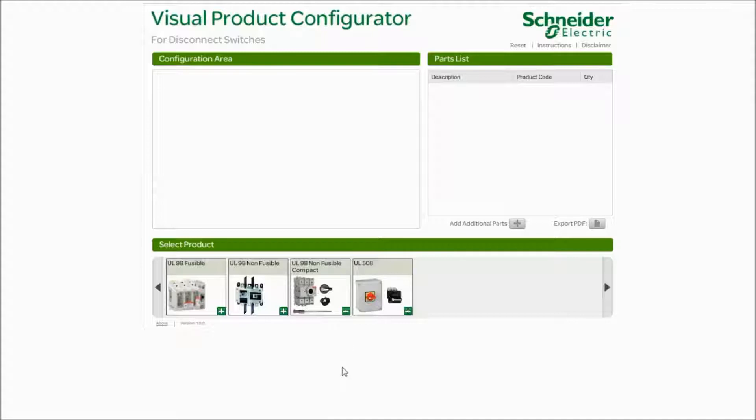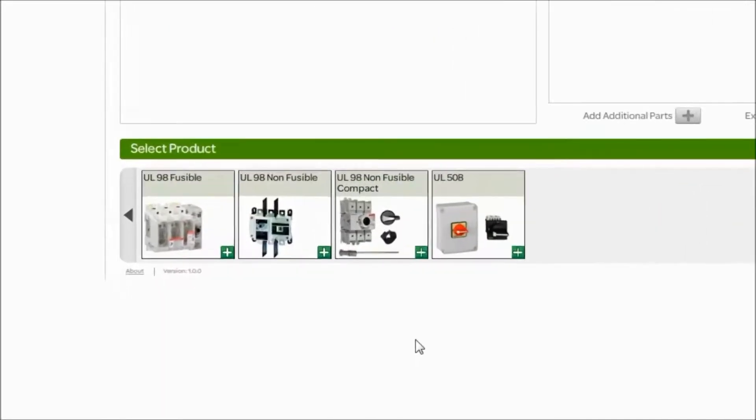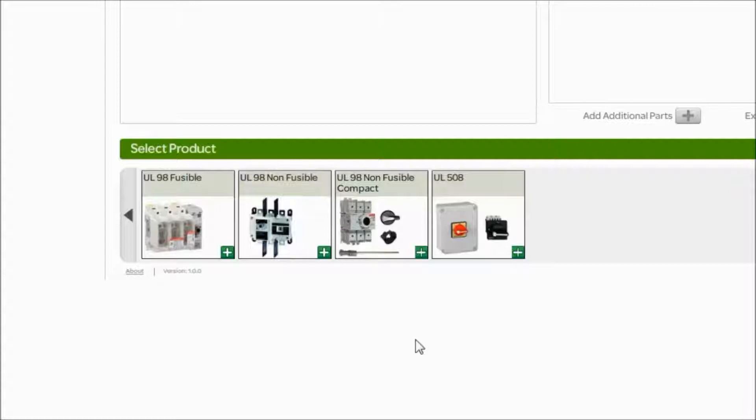The first thing that I want you to ask your customer when they tell you they need a disconnect switch is what is it for? Is it for a panel or is it for a motor? If the answer is their customer needs it for a motor, the answer is a UL508 type device. UL508 is only used for motors. UL98 is used for panels. You may use a UL98 for a motor as well, but your customer's not going to want to because it's a lot more expensive.